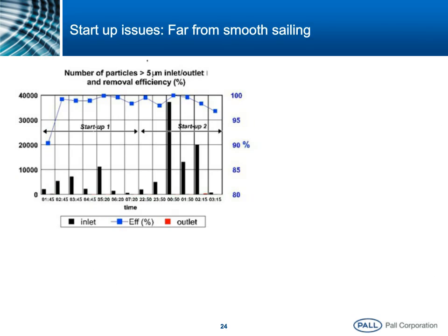And here we come to really the startup issue and the core of our problem. This is a little chart that shows the amount of particles present in water during a startup phase of a very large steam power plant. And you can see that the black bars are extremely variable, whereas the time frame itself is quite short. We're talking about a couple of days total represented on this chart. So you can see that overall the contamination is very unstable.